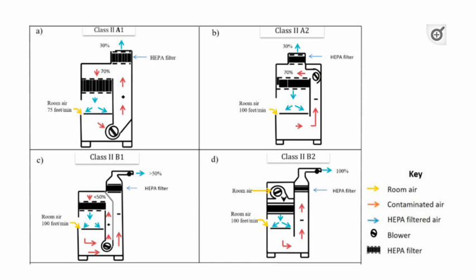Okay, so when we say class 2A1, when you hear A1, usually in the type 1 class 2 cabinets, their blower is located away from the filter. As you can see here, the class 2A1 and class 2B1 both have 1 in their typing because their blower is away from the filter. Now when we say class 2A2, when we say 2, the blower is usually near the filters. As you can see here, class 2A2 and class 2B2 have the same placement of their blower, which is near the filter.